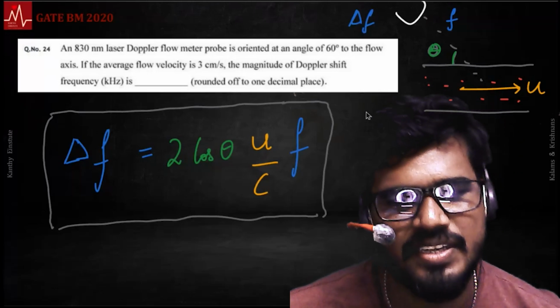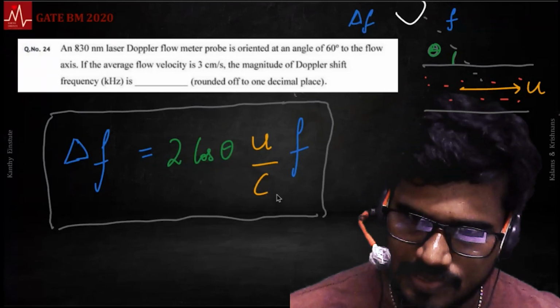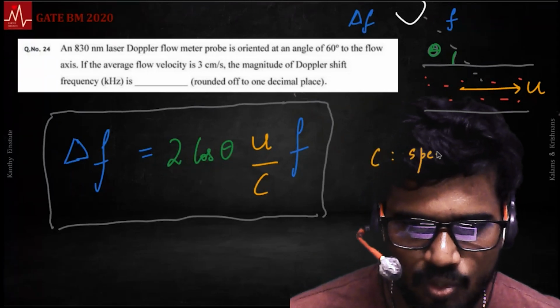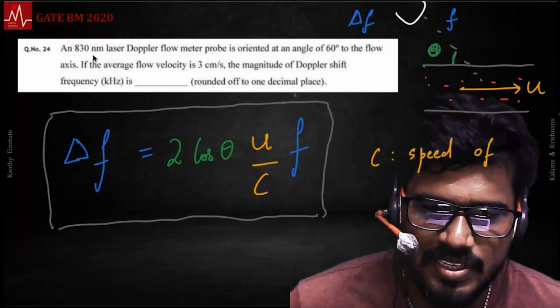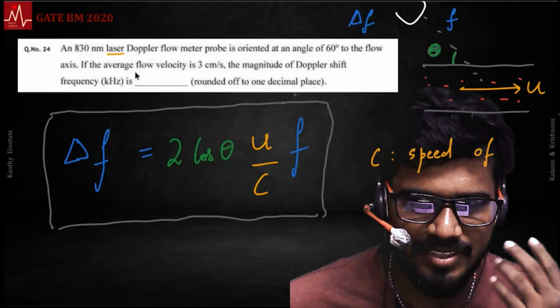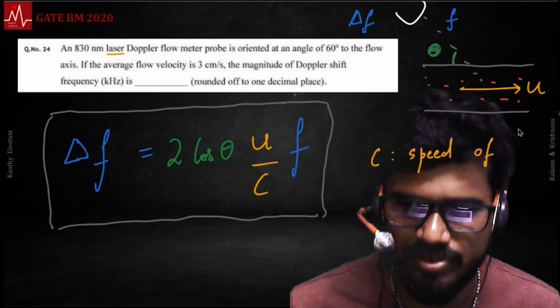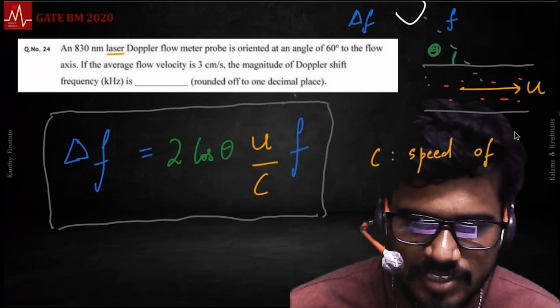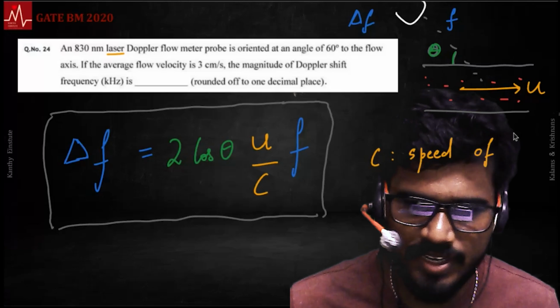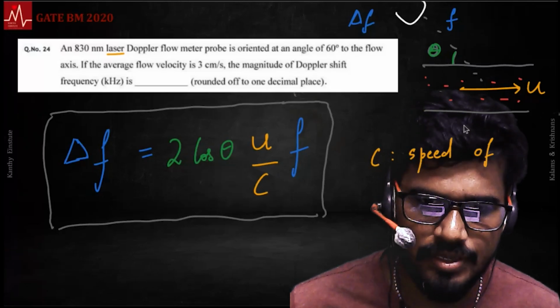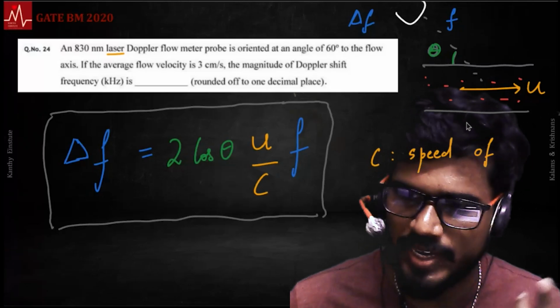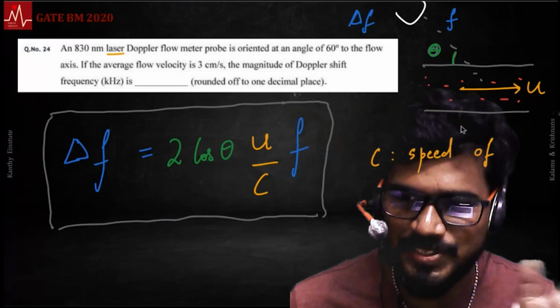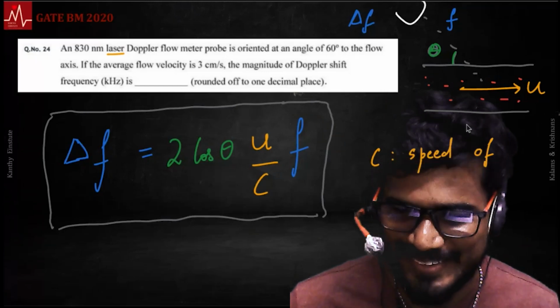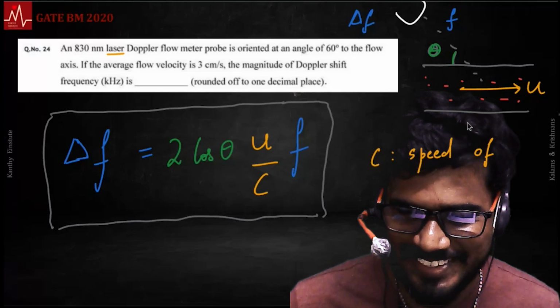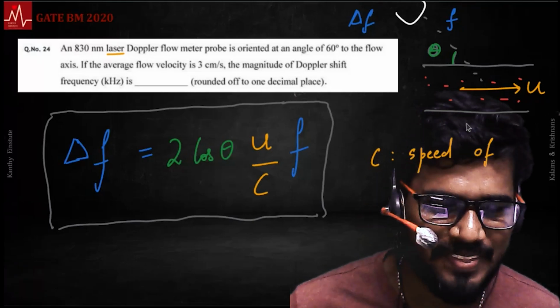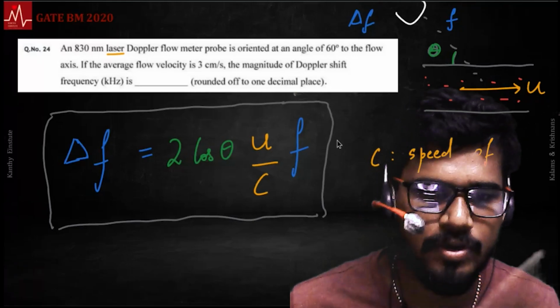And what is the C? We have to be careful. C is the speed of whatever the method is. If this is a laser probe, this is the speed of light. Be careful: just because it's Doppler doesn't mean it's the speed of sound. Doppler shift occurs with any wave, including light. Relative changes in velocity don't happen with light, since the speed of light is a constant, but the frequency of light will change. So Doppler shift, be it a sound wave or a light wave, does happen.